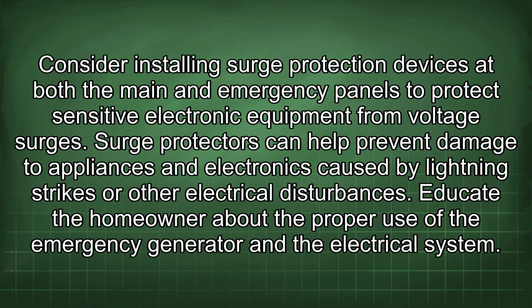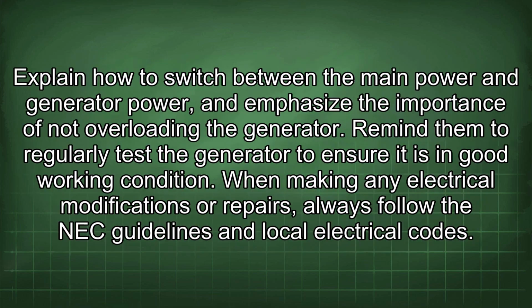Consider installing surge protection devices at both the main and emergency panels to protect sensitive electronic equipment from voltage surges. Surge protectors can help prevent damage to appliances and electronics caused by lightning strikes or other electrical disturbances. Educate the homeowner about the proper use of the emergency generator and the electrical system. Explain how to switch between the main power and generator power, and emphasize the importance of not overloading the generator. Remind them to regularly test the generator to ensure it is in good working condition.